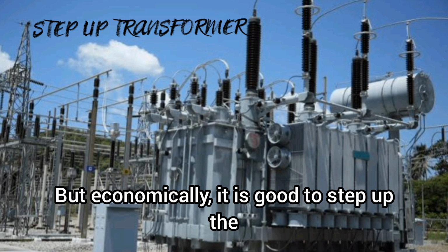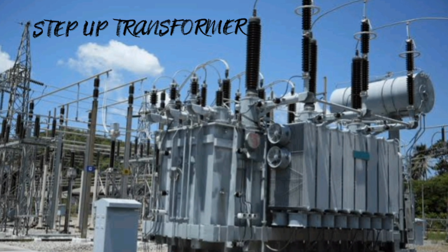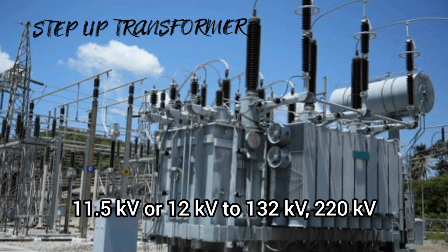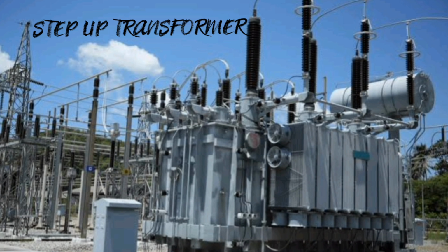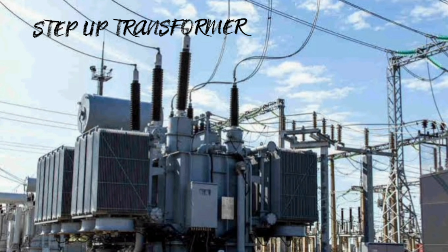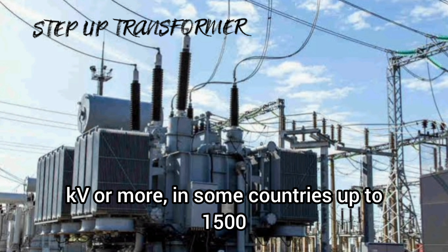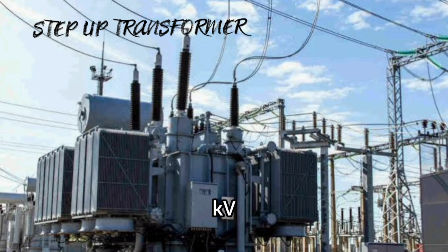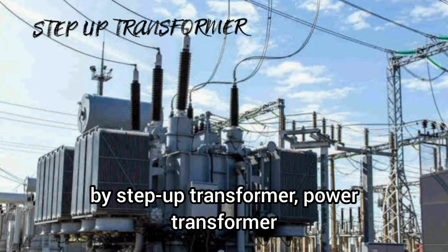But economically, it is good to step up the produced voltage from 11 kV, 11.5 kV, or 12 kV to 132 kV, 220 kV, or 500 kV or more. In some countries, up to 1500 kV by step-up transformer, power transformer.